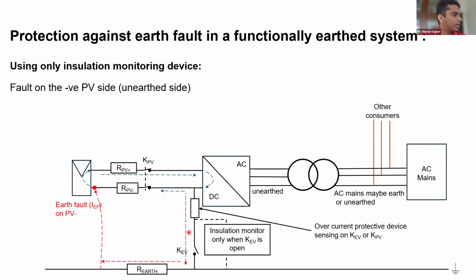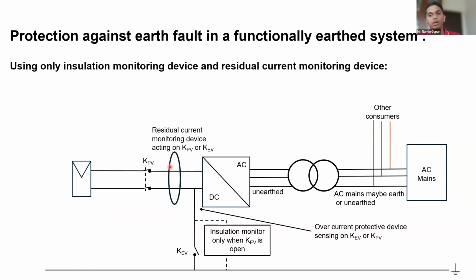Now, the functionally earthed terminal can be of two types. One, it can be an overcurrent protective device, for example a fuse, or it can also be a residual current monitoring device. If it is a residual current monitoring device, it is pretty easy. If there is an earth fault, obviously there will be a differential current, and with this differential current, this residual current monitoring device will be acting either on KEV or KPV. That depends on the inverter, and that depends on the designer. So this is how earth fault protection is done in a functionally earthed system.